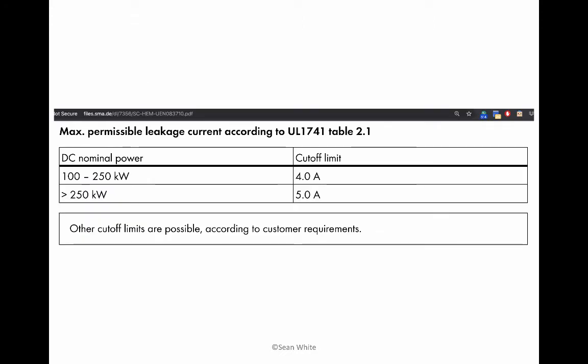Now here's something kind of interesting. This is for UL 1741, and I got this from a large SMA inverter. They are talking about when it has to cut off, and this would have been for a fuse grounded system, and sometimes we still use fuse grounding for larger inverters. Between 100 and 250 kilowatts, you could have 4 amps of leakage current. That is current going down the equipment grounding conductor to the inverter through the fuse. So if you had a 1 amp fuse in these cases, it wouldn't work.